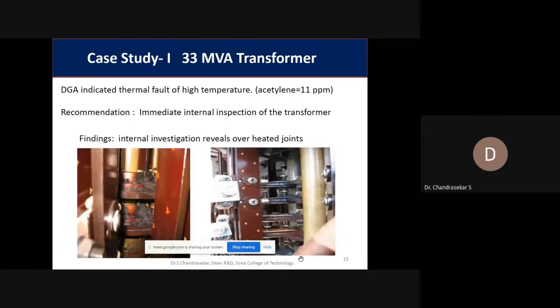For example, you can see some of the case studies here. A 33 MVA high voltage transformer had a fault. When we inspected inside, we found overheated joints. In the joints, continuous arcing happened, and therefore you can see that complete blackish portion. It is because of continuous arcing, or partial discharge, occurring in those portions due to the overheated joints.